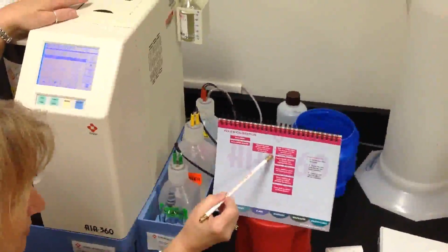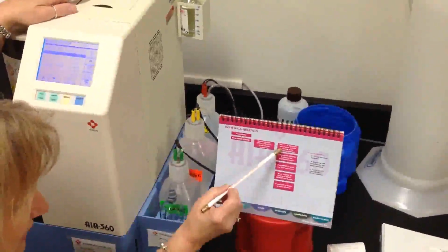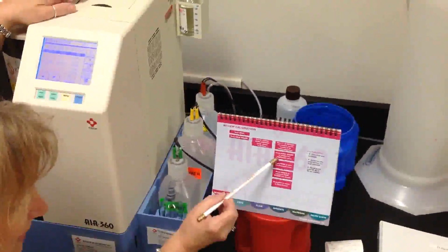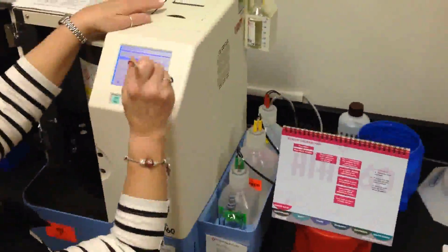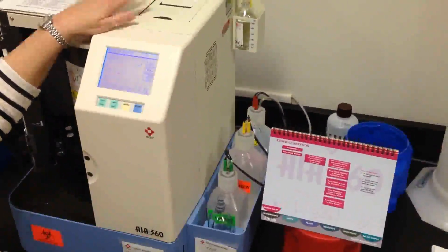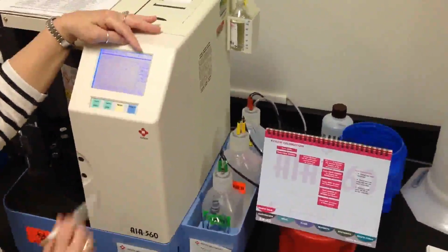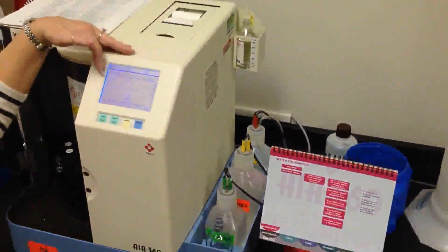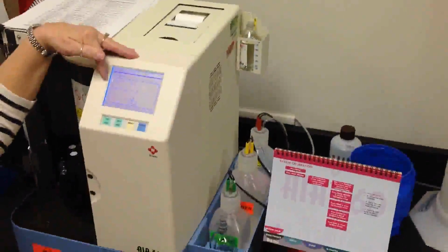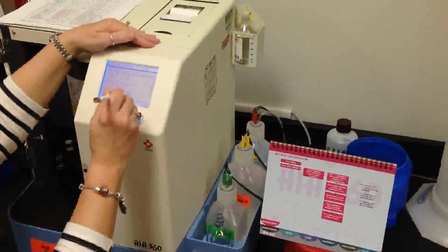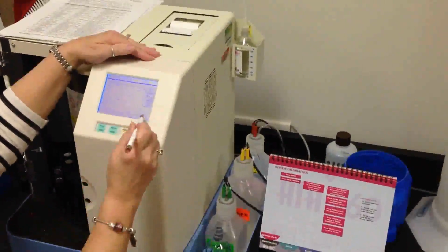I'm going to use the highlight keys to review. I want to calculate, and it draws my curve for me. Okay, so I will press accept, and it's telling me I have an error message because it already has a calibration in there.